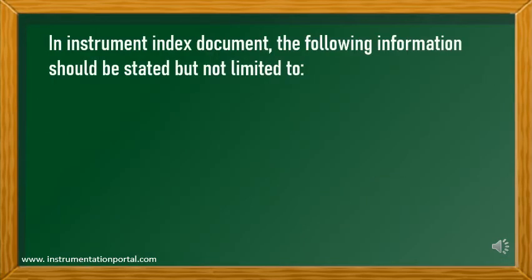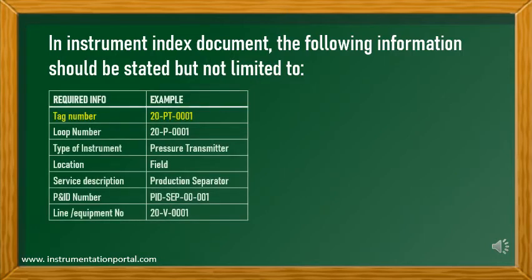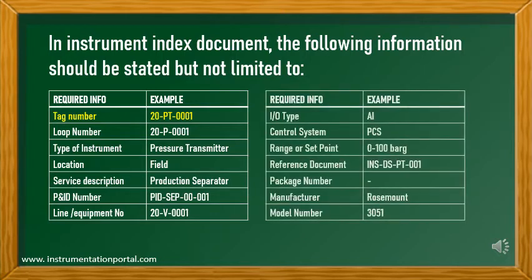In the instrument index document, the following information should be stated but not limited to: tag number, loop number, type of instrument, location, service description, P&ID number, line number or equipment number, input/output type, control system, range or set point along with engineering unit used, applicable reference documents such as instrument data sheet number, hook-up drawing number, instrument layout number, loop drawing number, package number, manufacturer, and model number.